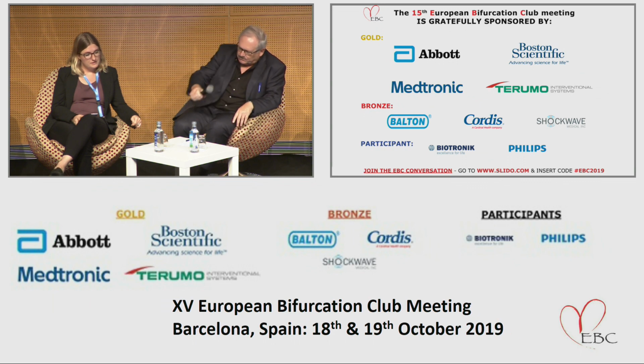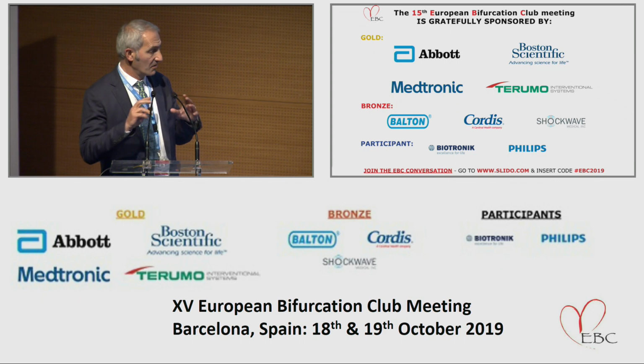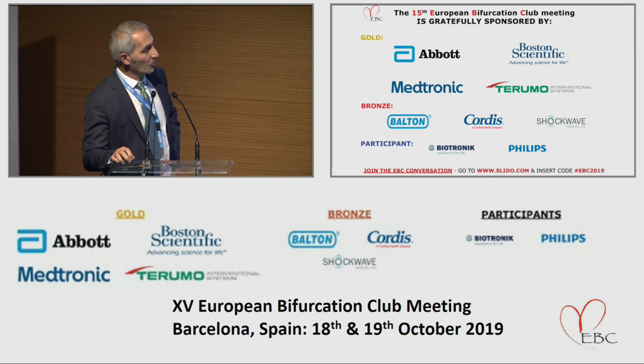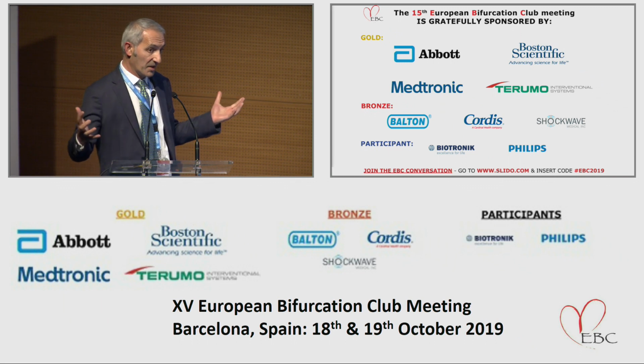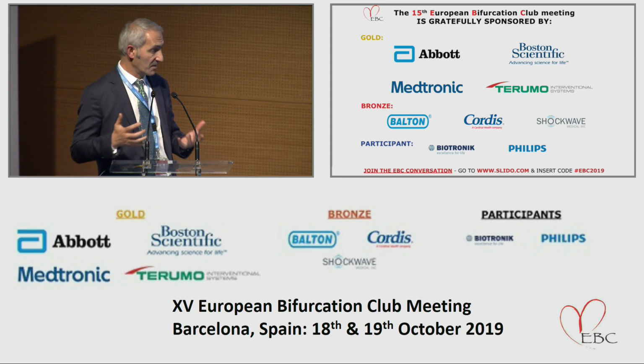Yeah. I mean, we know that the big boxy struts are not good, right? We've known that theoretically, and work from your lab and other labs have shown, and our lab a little bit, that basically you pay a price for the low wall shear stress when you have the big boxy struts. So we know smaller struts are better. We also know that round struts generally are better than square struts.